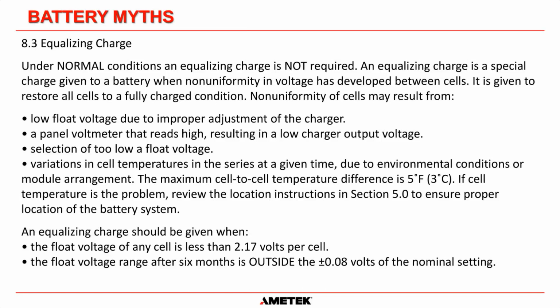So this is from a battery manufacturer's manual, and it says under normal conditions, an equalizing charge is not required. Then it goes on to say what an equalizing charge is. But the most important thing is this one down here. An equalizing charge should be given if the float voltage of any cell is less than 2.17 volts, or the float voltage range after 6 months of a cell is outside the plus or minus 0.08 volts.